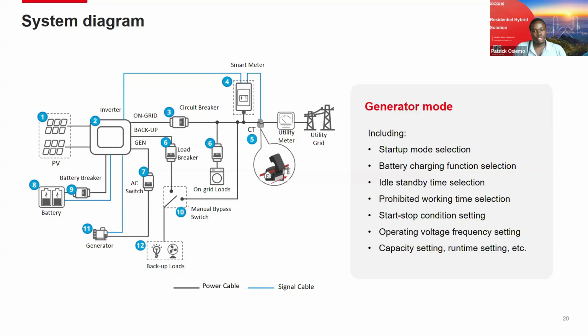And when the generator is operating, the inverter is capable of a number of functionalities. Apart from starting up and stopping the generator, it's able to prohibit the working times of the generator, or you can set up the idle or standby time of the generator, operating voltage and frequencies. You can set the capacity of the generator and the runtime settings. So that's the high level control capability of the ES unit with reference to the AC generators connected to it.